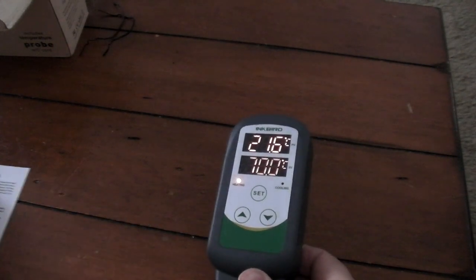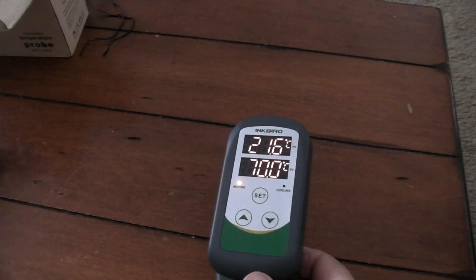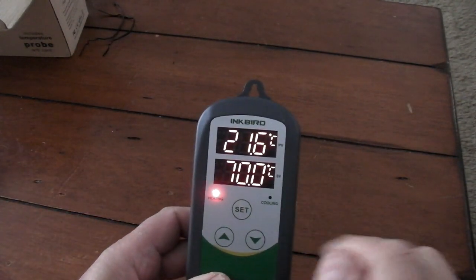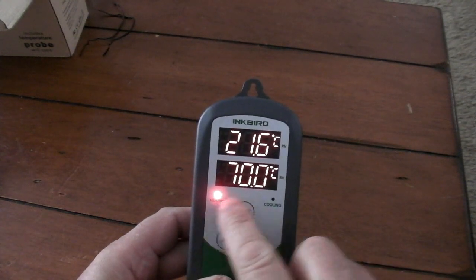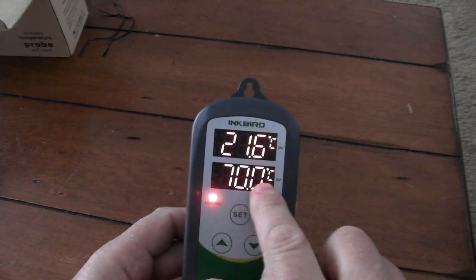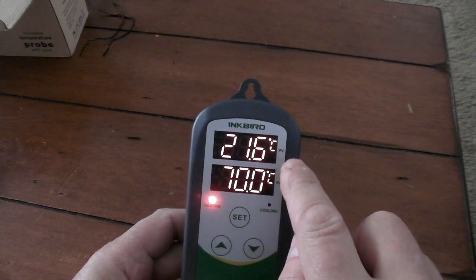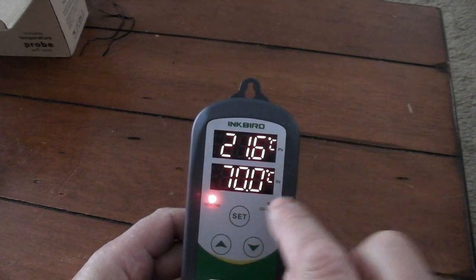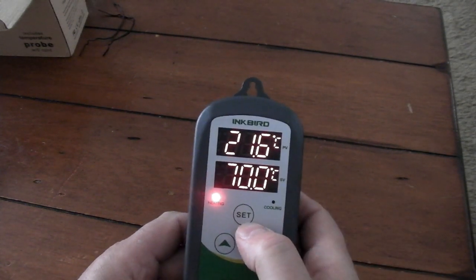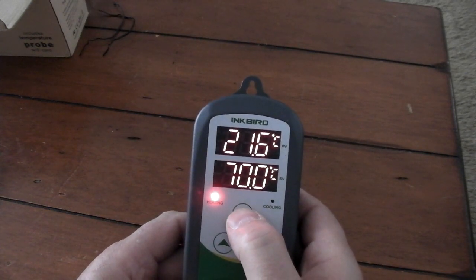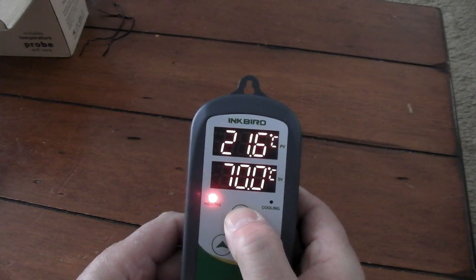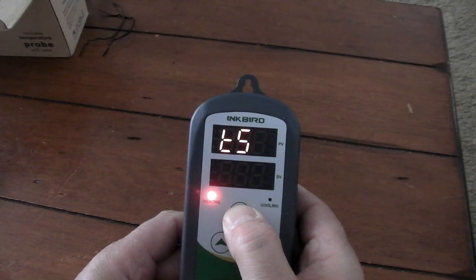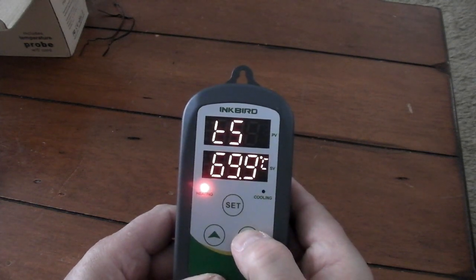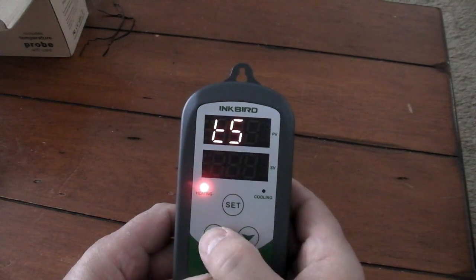Okay, so when you first turn your Inkbird on, it may be set like mine is in centigrade, and it's on heat mode. So it depends on the temperature it's set at. It'll be in heat mode or cooling mode depending on what the number is in that window there. So you're going to want to hit set, press and hold it for 3 seconds, and then you can scroll between the different options here.